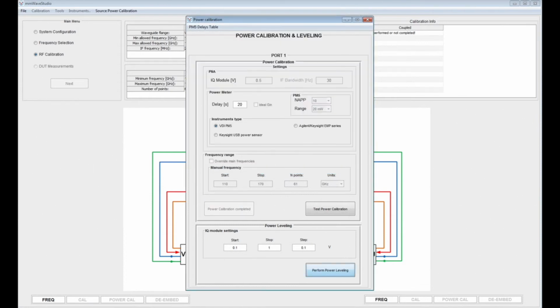The second step that we need to do for power calibration is power leveling. Because the frequency extenders are highly nonlinear, we need to characterize that nonlinearity so we could perform the power sweep measurements and apply power control to the S parameter extraction. In the start and stop boxes, we type in the start and stop voltage values that will be applied to our IQ modulators in the vector modulation unit. We then also need to specify the desired step size for accurate characterization of the frequency extender turn-on characteristics. Now we can perform power leveling.